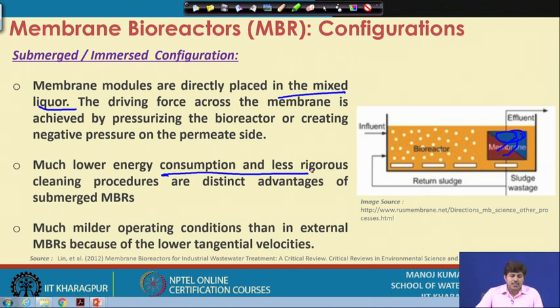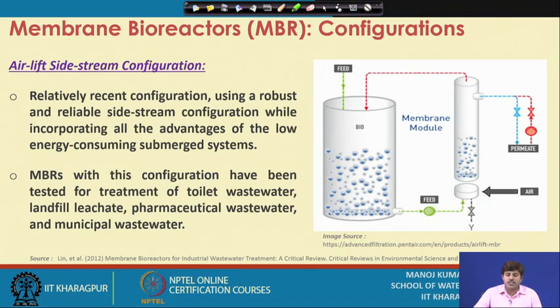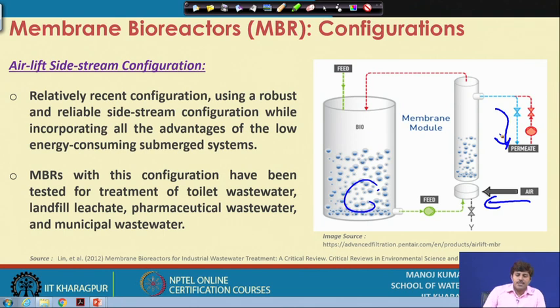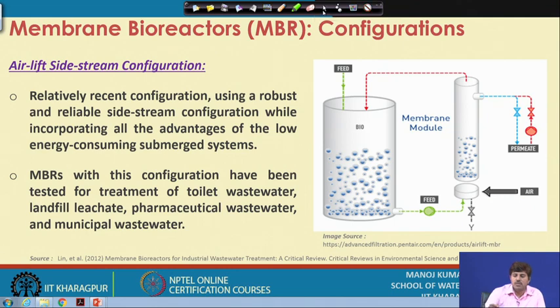The operating conditions of submerged MBRs are milder than external MBRs because of lower tangential velocities. The third configuration — the air-lift side stream configuration — uses air feed and feed coming from the bioreactor, then passes it through a membrane module to collect the permeate. This relatively recent configuration combines the robust and reliable side stream setup with the low-energy advantages of the submerged system, and has been used for treating pharmaceutical, landfill leachate, toilet wastewater, and municipal sewage.